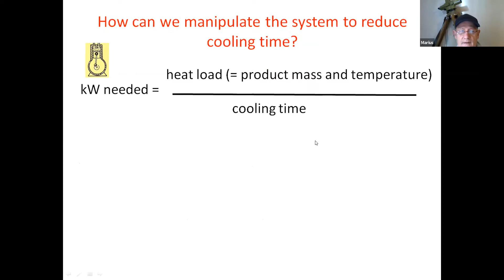So how can we manipulate that system? It's basically the same formula I've just shown you, looking at the two scenarios. And this is where the table grape industry is now, where they are at the moment. They've got this existing capacity in many of their cold rooms designed for a certain heat load, for a certain cooling time. And what they've done now is they've said, okay, you need to cool faster. This cooling time has changed. So unless you change the heat load, it's impossible to maintain the same sized system and reduce the cooling time without messing with the numerator in this little sum. So the heat load needs to change. You either reduce the heat load by putting in less product, or you bring in cooler product. That's basically what you have to play with.